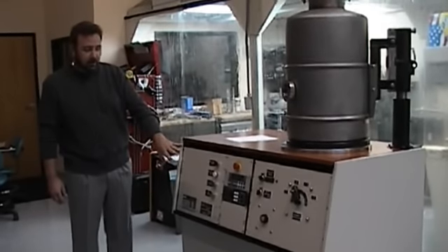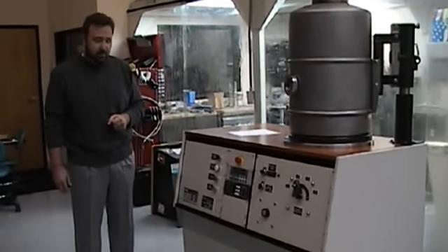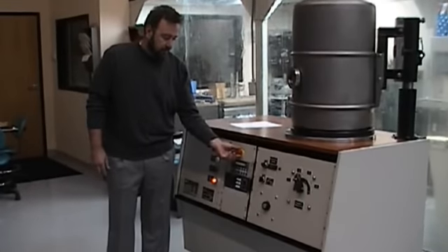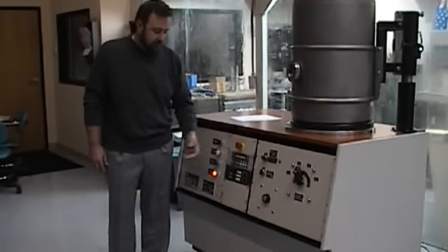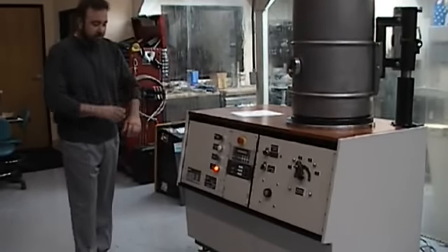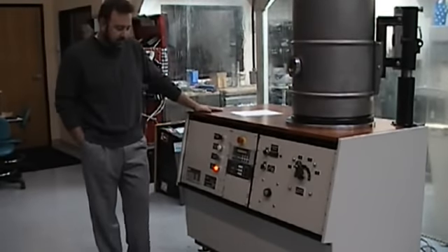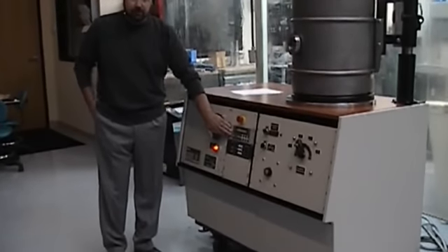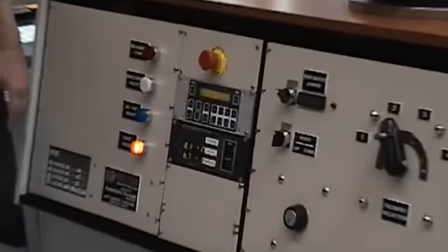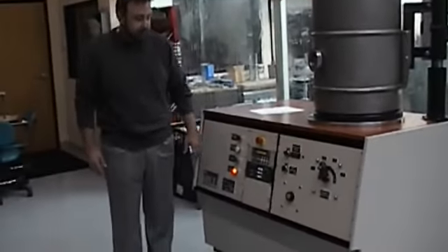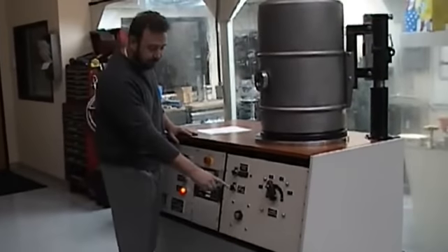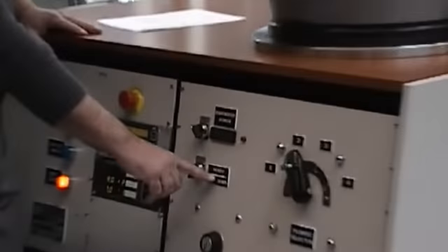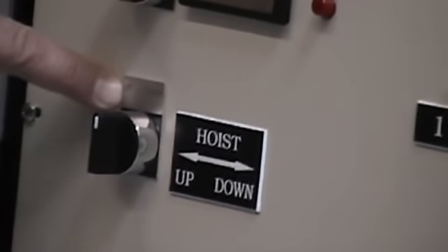So as the cryo pump is still running, we need to shut down the compressor, which is on separate power supply. When you re-engage, you simply twist turn, everything should come back to the last status where it was, including the evap valve, which it has. It's in the closed position, it is vented, and now we're ready to open the bell jar. The hoist is located, our labels are here showing clearly the up and the down position.